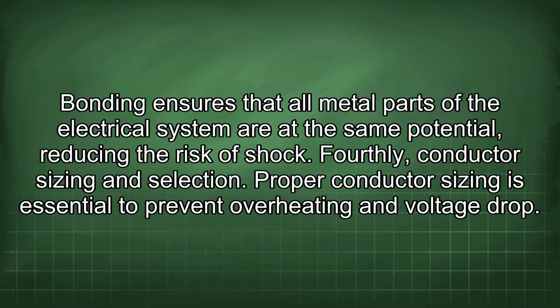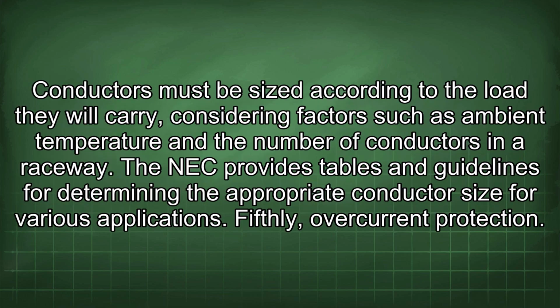Proper conductor sizing is essential to prevent overheating and voltage drop. Conductors must be sized according to the load they will carry, considering factors such as ambient temperature and the number of conductors in a raceway. The NEC provides tables and guidelines for determining the appropriate conductor size for various applications.